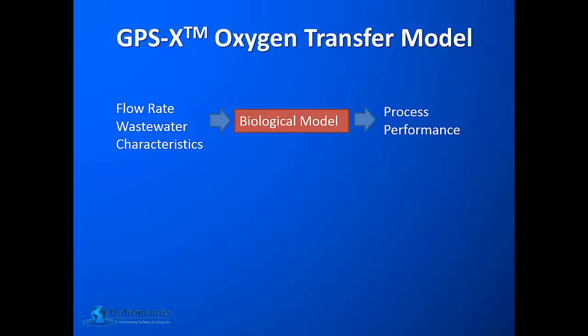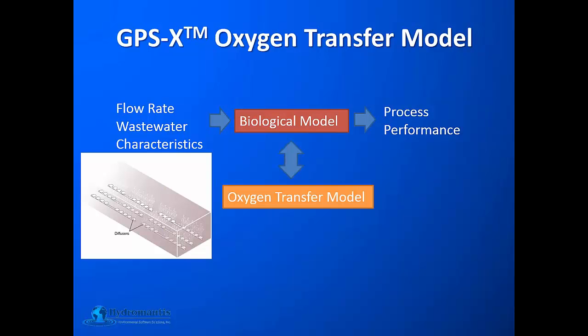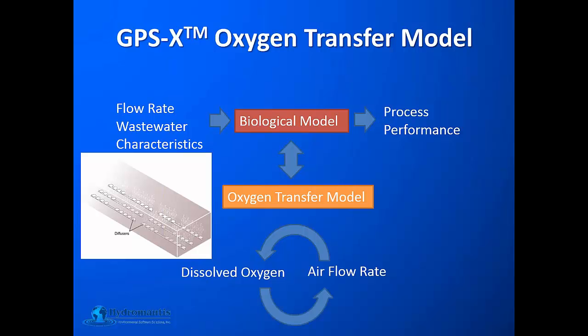Typically, models handle oxygen transfer in the biological model by including an oxygen transfer model that allows the user to either specify a set dissolved oxygen concentration in the aeration tank — which helps determine the air flow rate — or specify the air flow rate from which the dissolved oxygen concentration can be calculated. In this model, we are not modeling any of the head losses that may happen in the air delivery system.